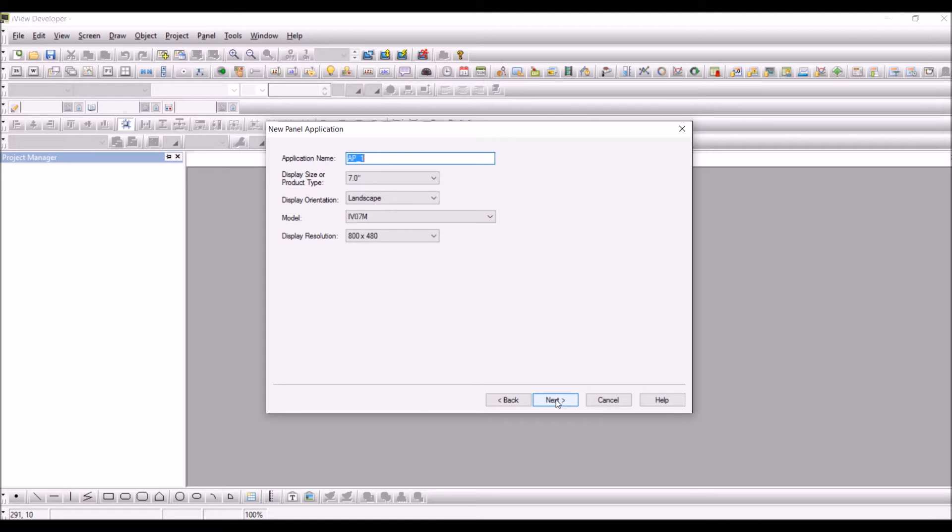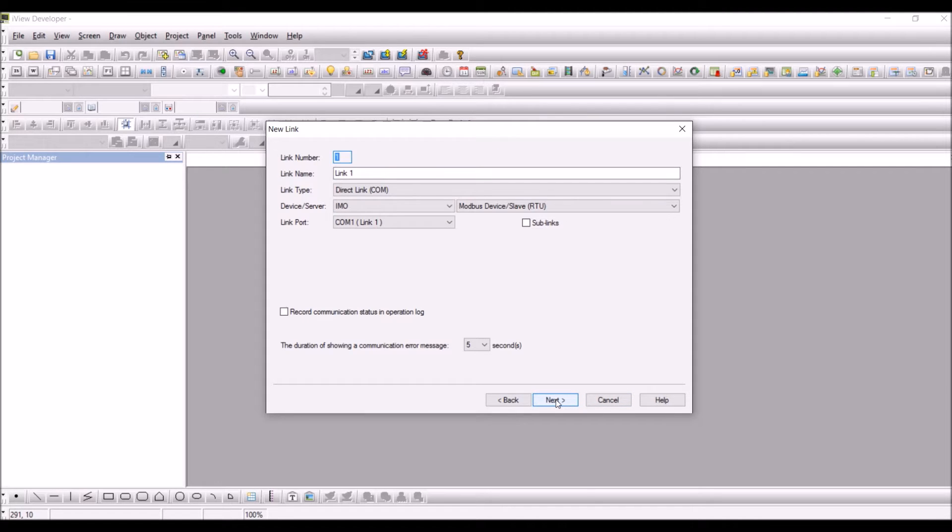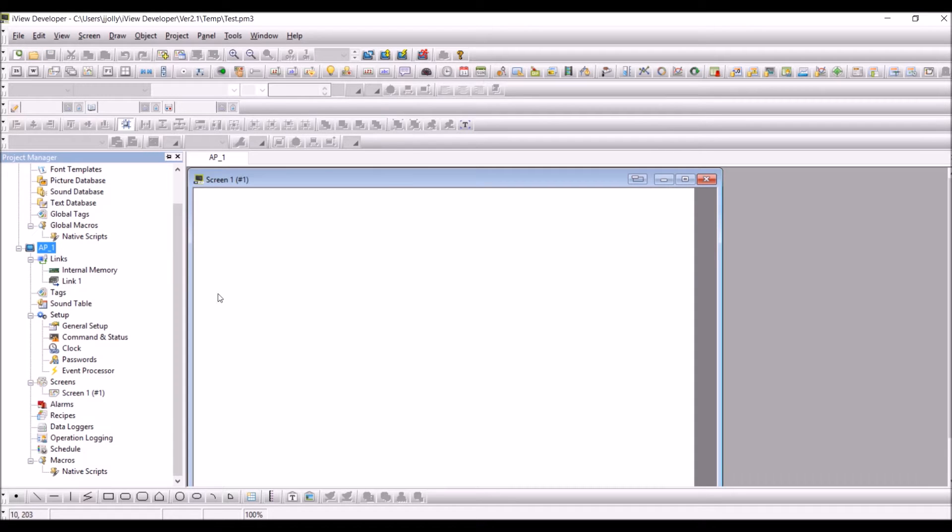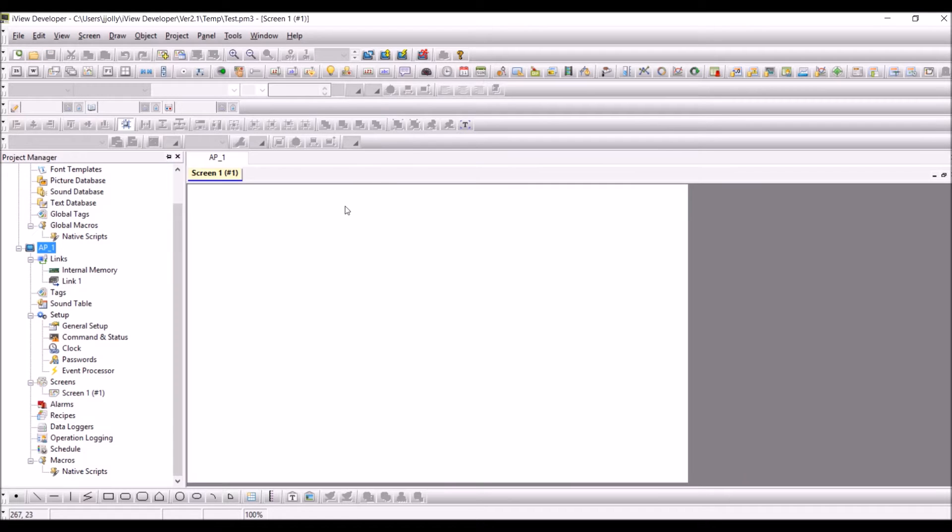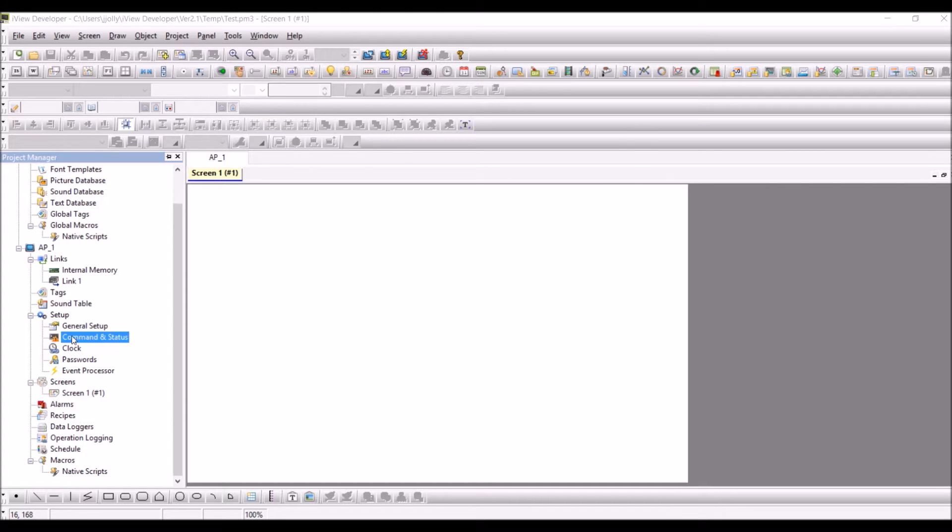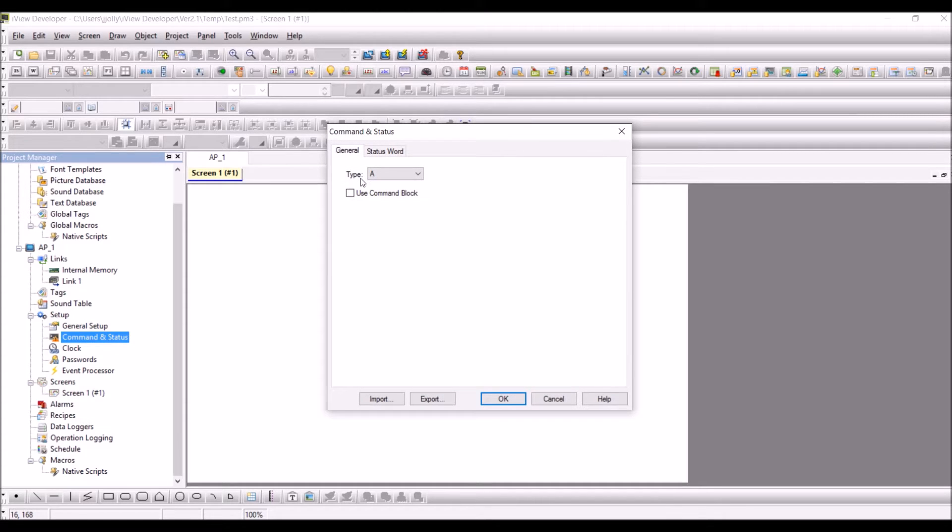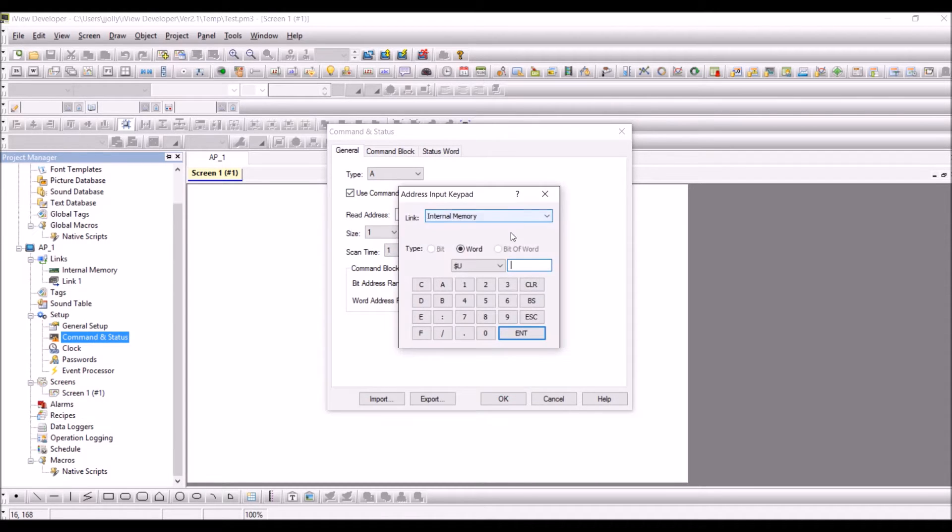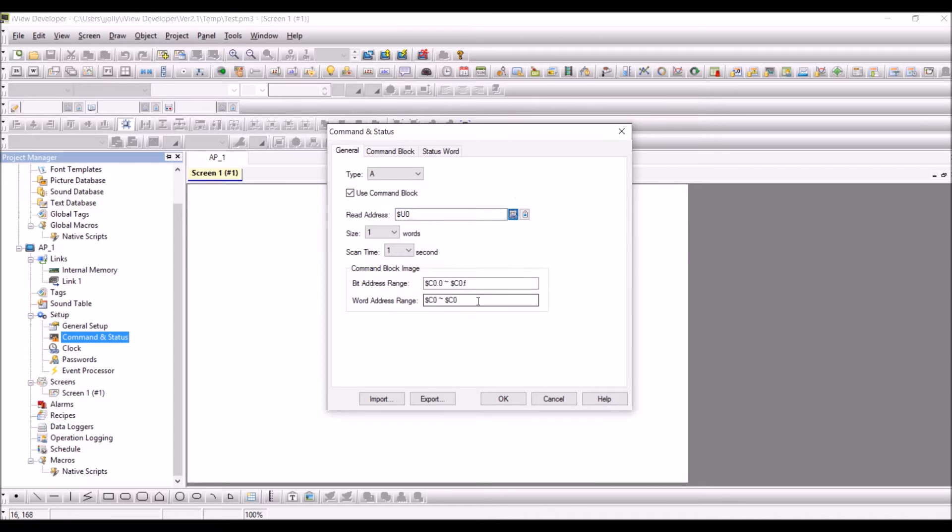Configure all the drivers and then go to the command and status under setup. Click on use command block and configure a read address. This is just for example, you have to use the unused registers.